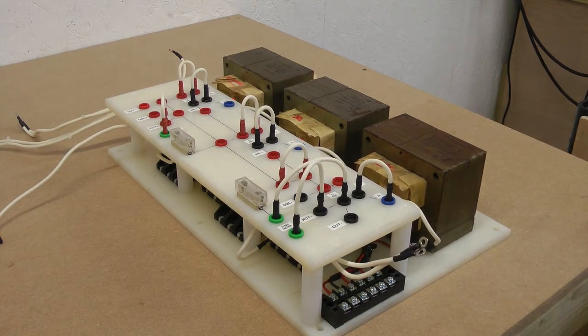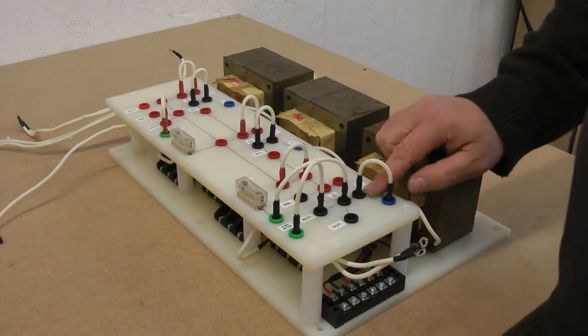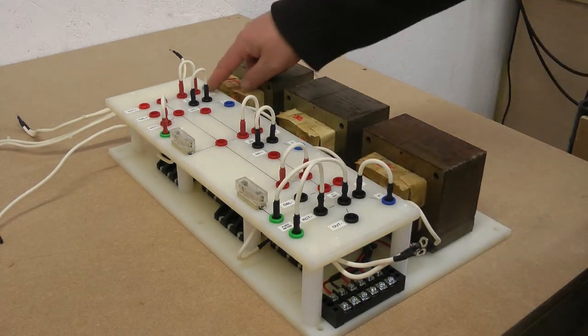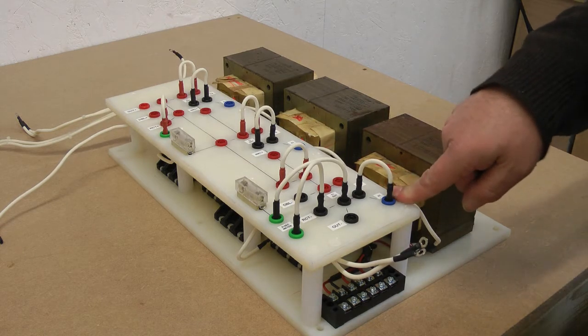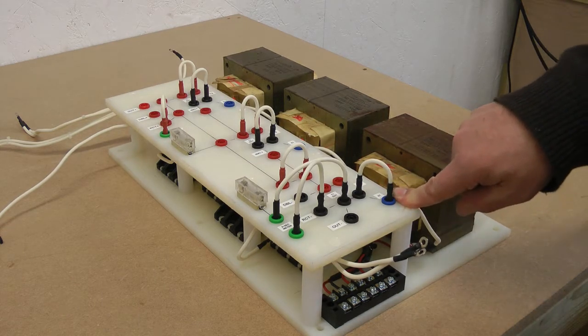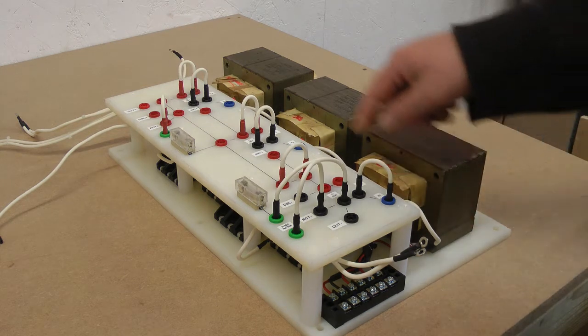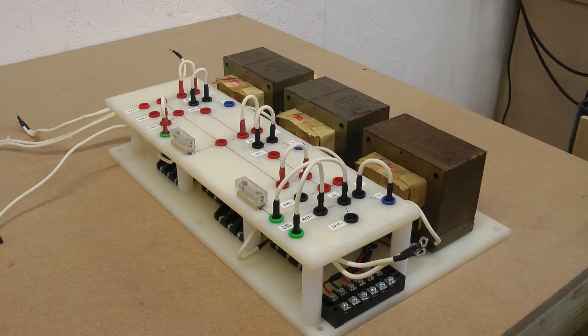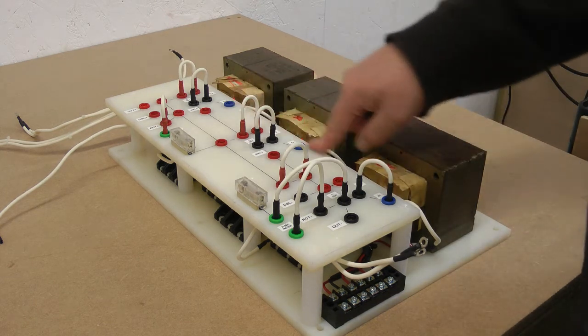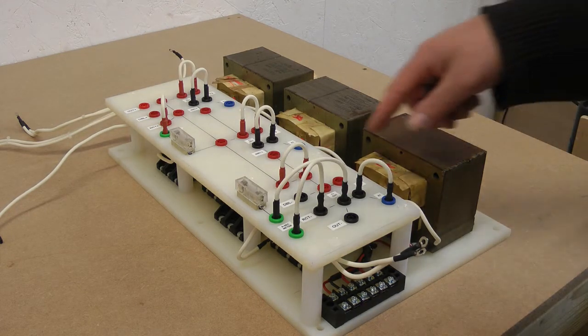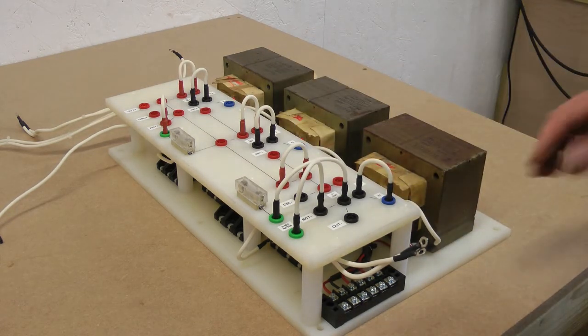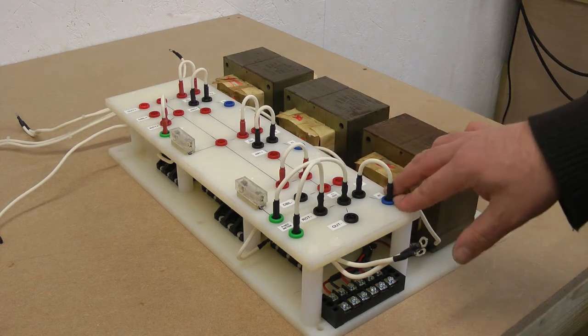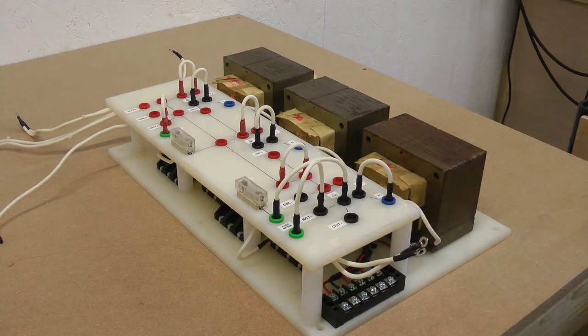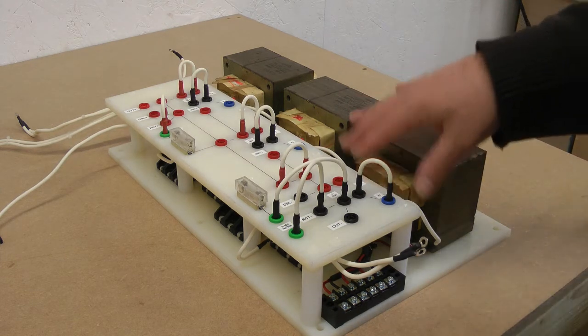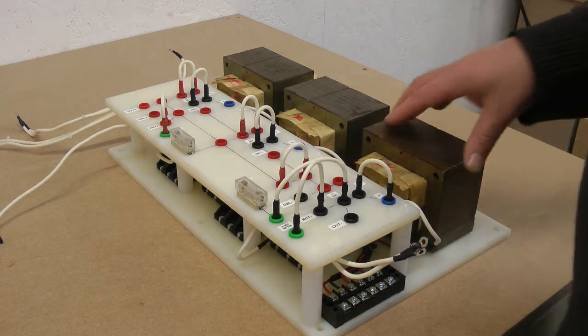In fact, we'll go through this now, since I'm on this point. First of all, there is a common earth line that doesn't necessarily connect to the line supply earth. You can disconnect that, so I distinguish them as a transformer earth and a line supply earth. This is the transformer earth. It also connects to outputs on the back panel, which are transformer earth, and there is a jumper at the other end at the line input, where you can connect transformer earth and line supply earth together if you need to. In some scenarios you do, in others you don't.